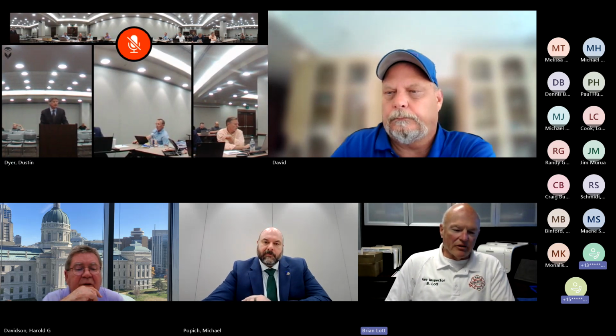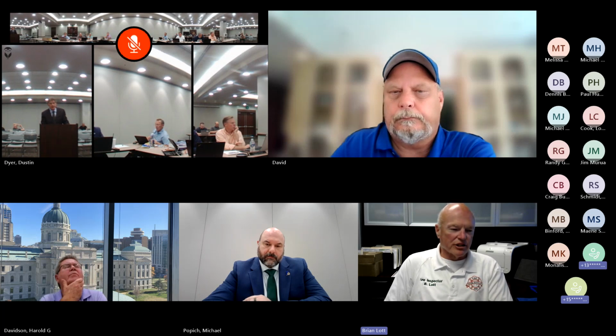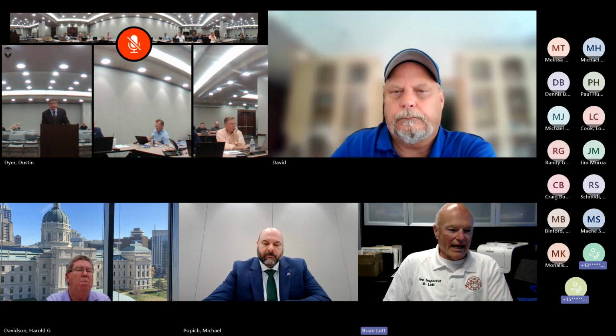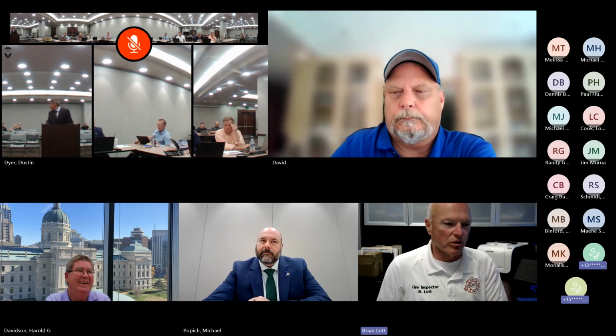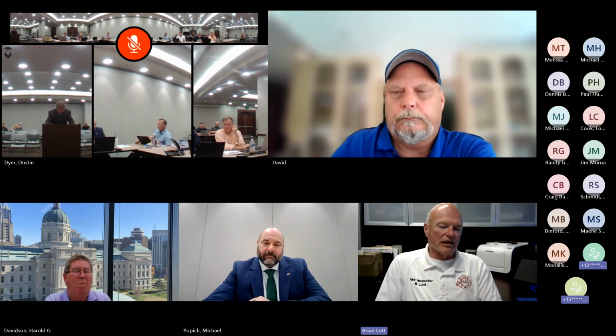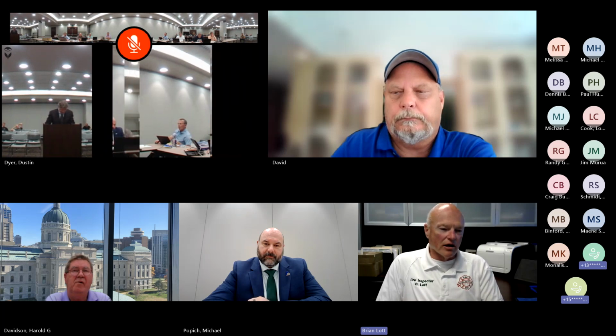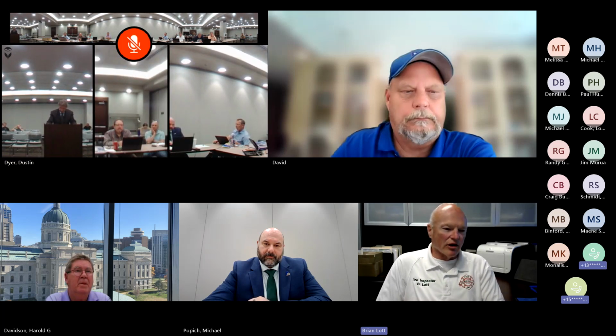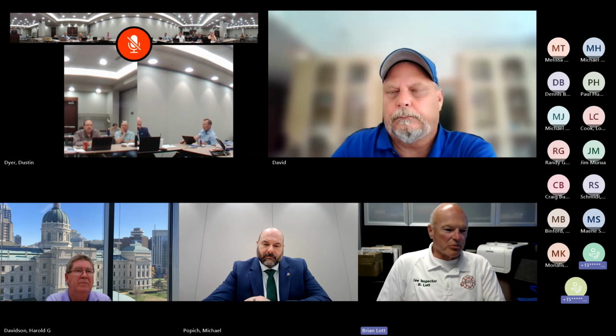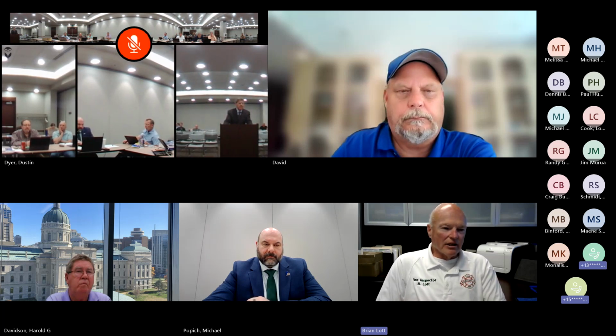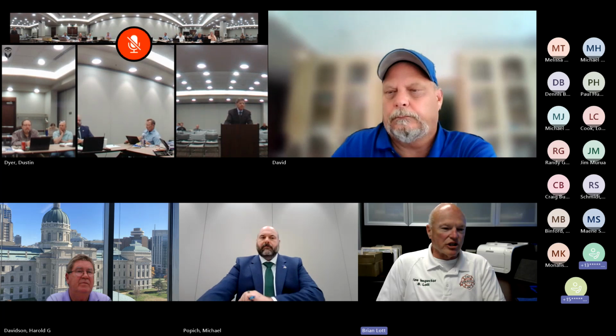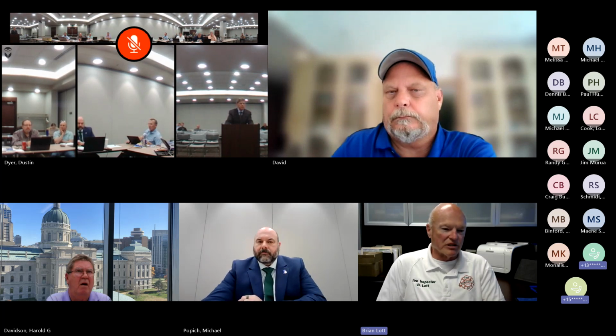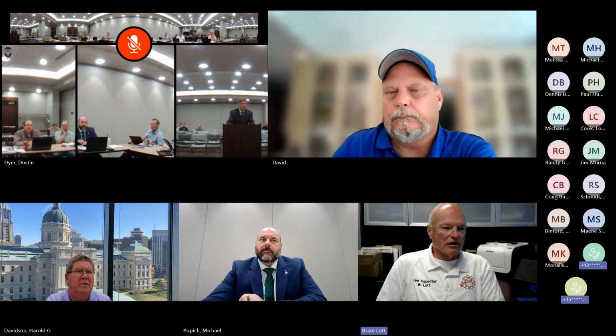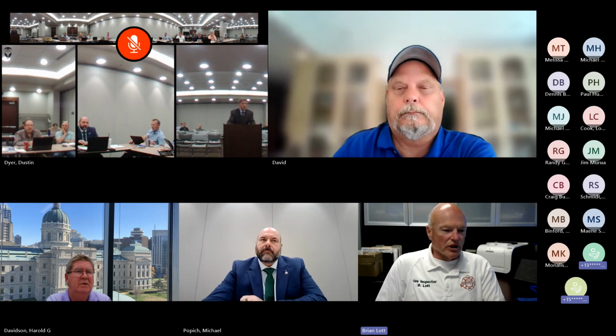Basically what happened on this project is the sprinkler contractor got lazy and installed what he had left on the job, which was 60% standard response heads versus the quick response heads that were designed for these balconies. They're all 155-degree heads. It's just going to take longer for the head to pop with a standard response versus a quick response. The problem now is changing those out. It'd affect 59 apartments, and they'd have to rip the ceiling back about 2 feet to change these heads on all the balconies, which is the hardship due to the cost to do that.